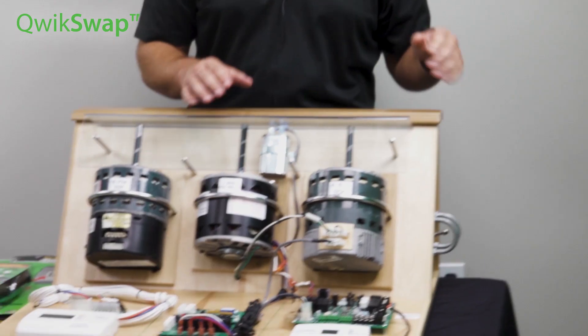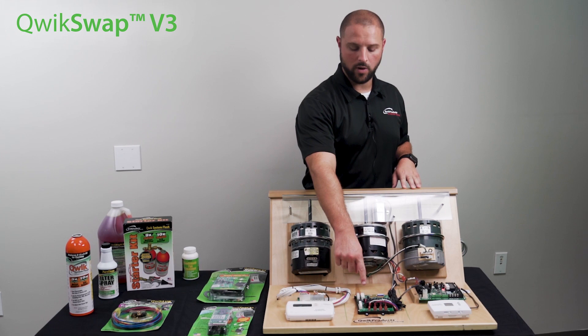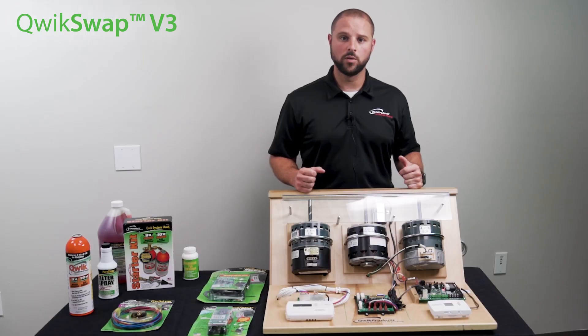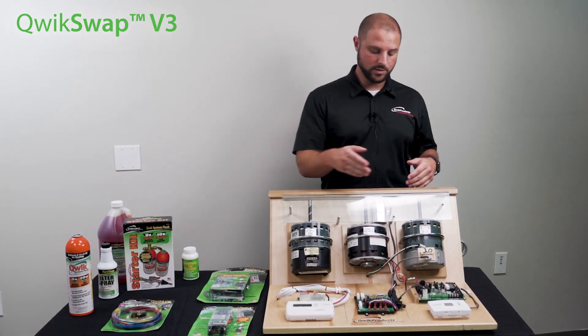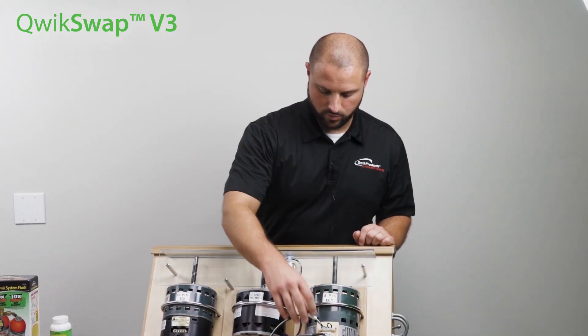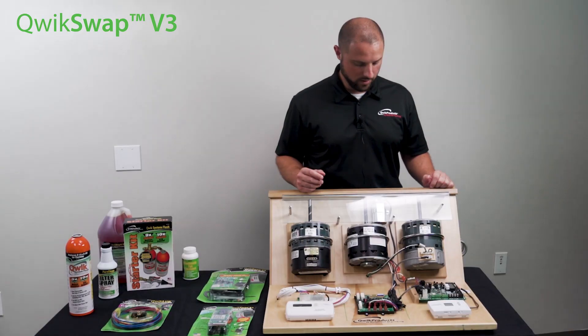And then this demo display right here — I'm going to turn the power on for you — this demo display right here, I actually have our QwikSwap V3 right here in the middle. QwikSwap V3 is actually going to replace any variable airflow ECM motor that's on the market, whether it's a 4-pin or 16-pin communication plug. In this demo, I actually have a 4-pin running. As you can see, this has got the two plugs — the top plug is the power plug, and the bottom plug is the communication plug.